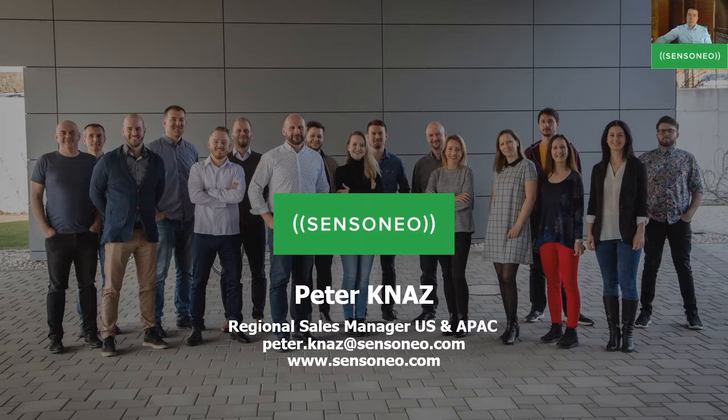The second question, which I see here: in silos there is a lot of dust, like from grain crops. How do you solve this dust covering the sensor eyes? Okay, so there is still something that we need to clarify about the sensors. So we use ultrasonic sensors. So ultrasonic sensor is not optical sensor. So optical sensor, once it's covered with dust, once the visibility from the optical sensor is really bad, in those cases the measurements are distorted right away, and you have very bad numbers, and you would realize that, okay, you need to go there and wipe the optical sensor, because it's really dependent on that view from that lens. Our sensors are ultrasonic sensors.